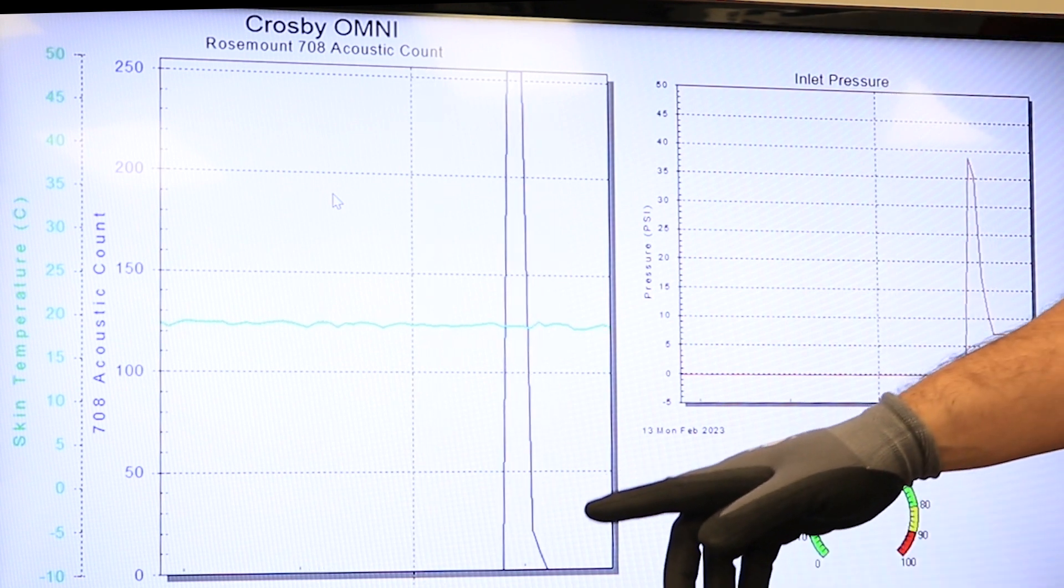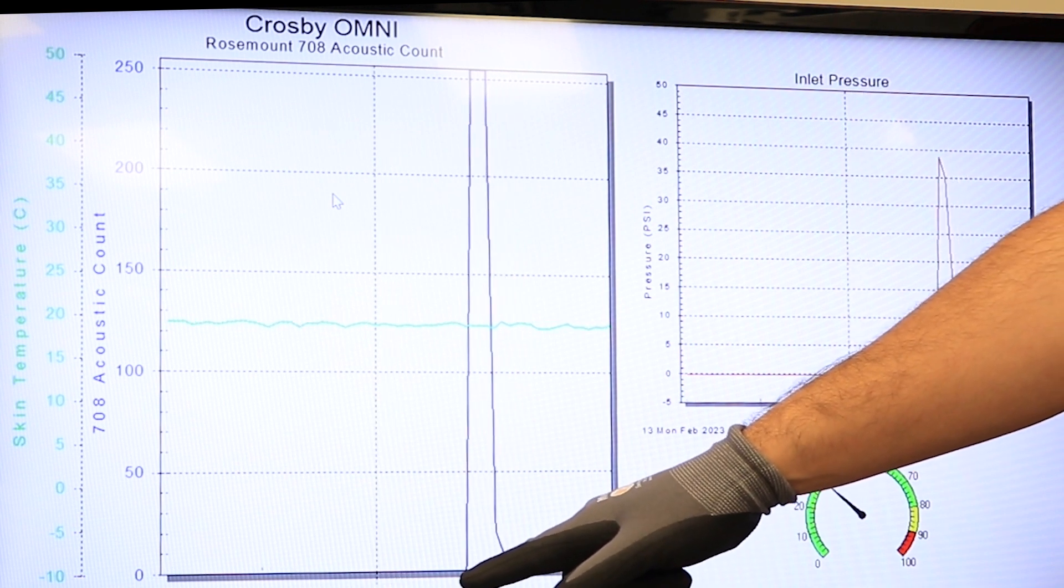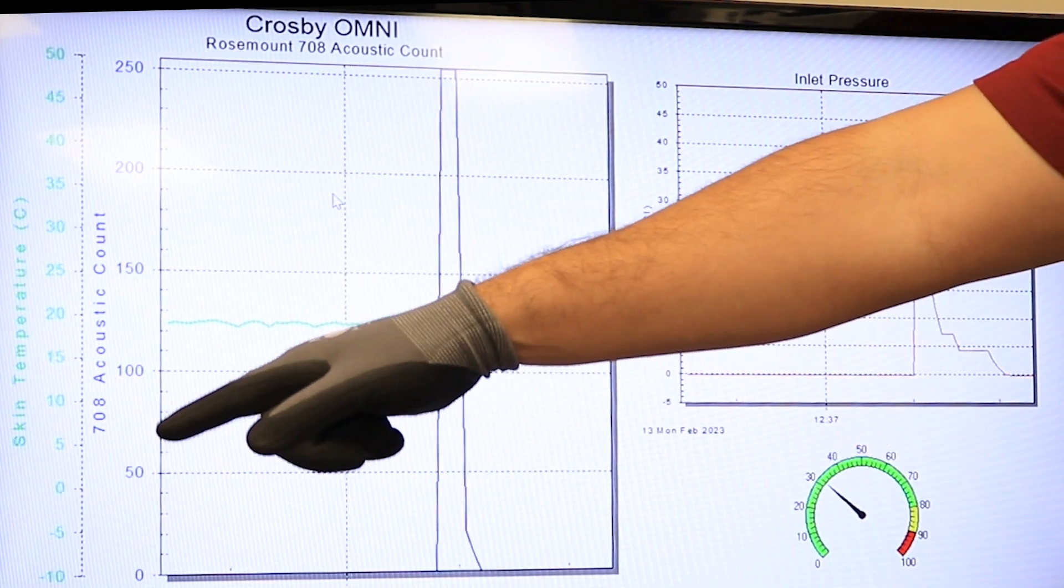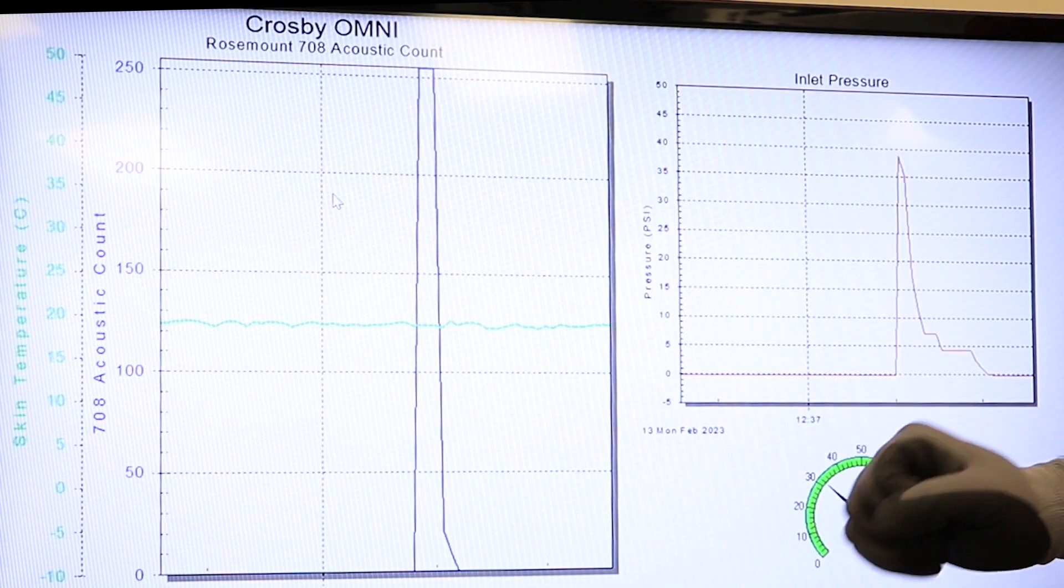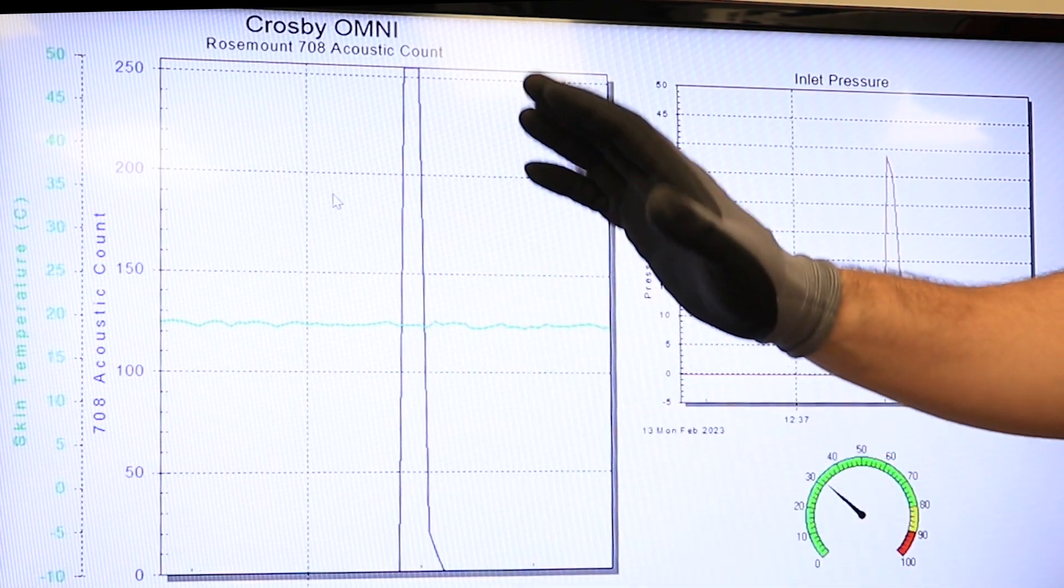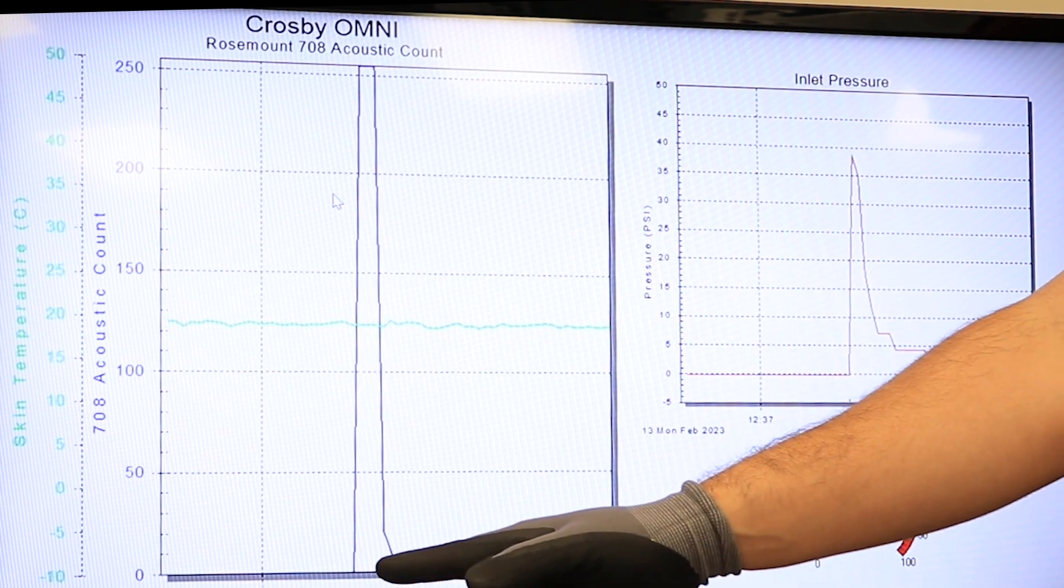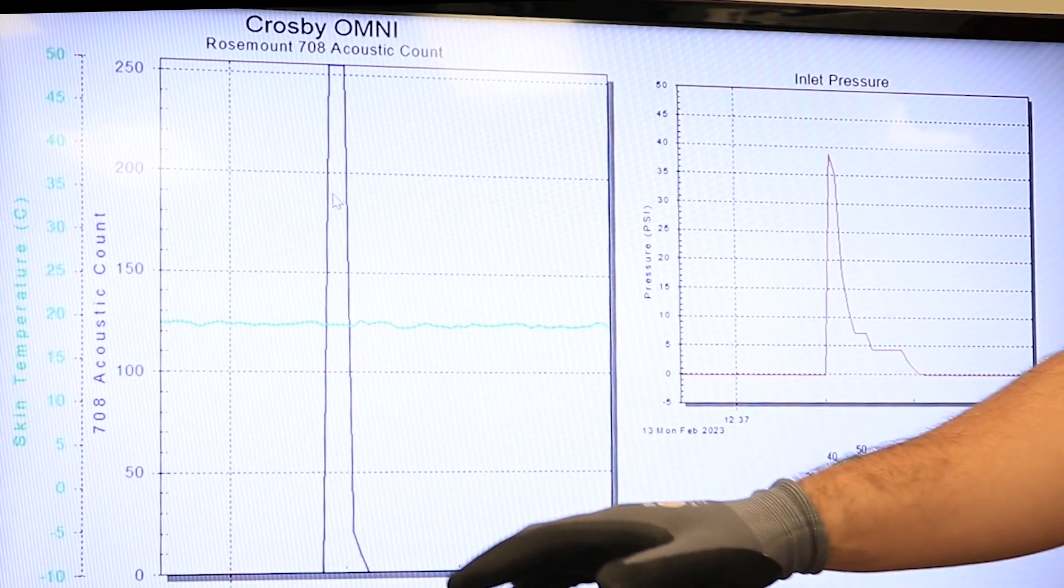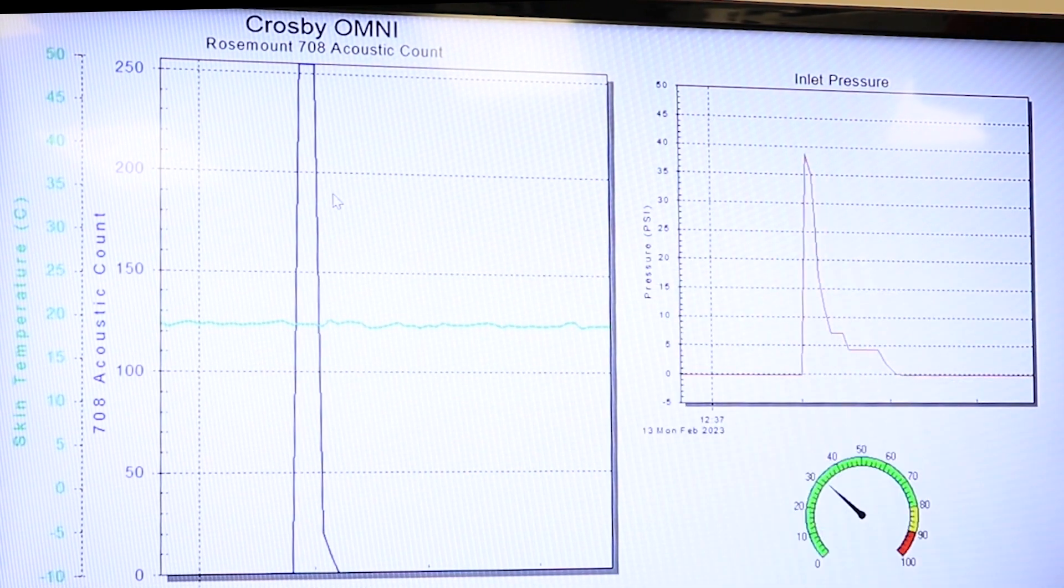As we can see here, the graph shows us when the valve opened and when the valve closed. There is no way to correlate the acoustic counts to how much the valve was opening. So, basically the information that we get from the 708 is discrete. Valve is closed all the way up to here and then it opens and it recloses at this point, giving us a time stamp of when the pressure relief event happened as well as the duration of the pressure relief event.